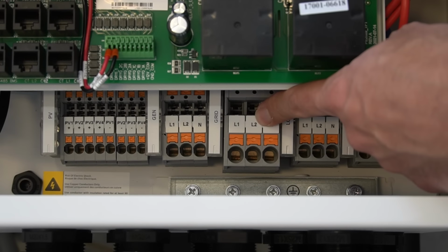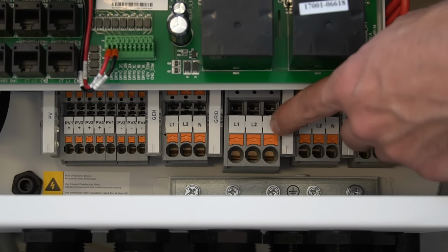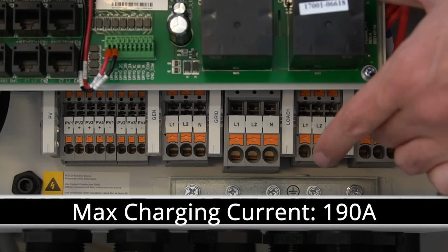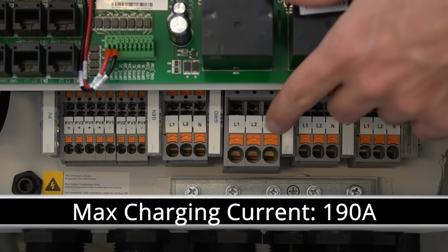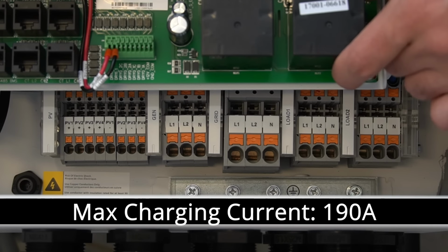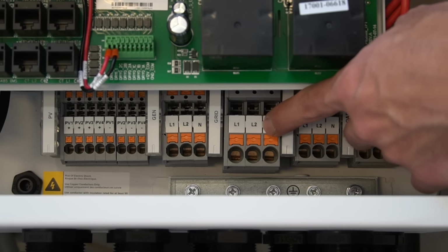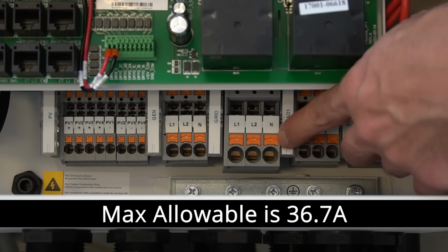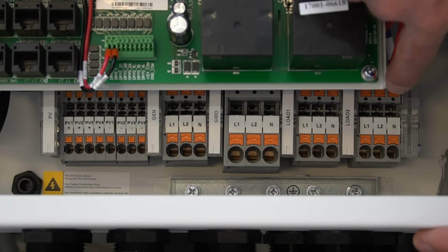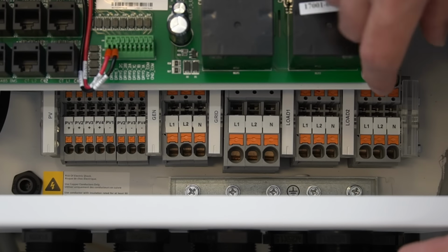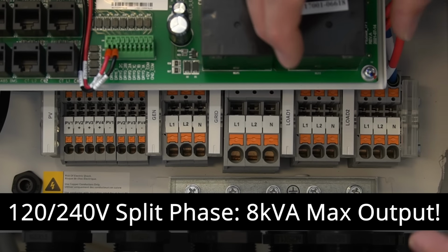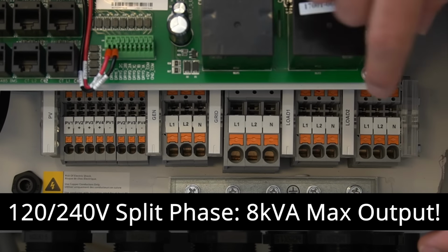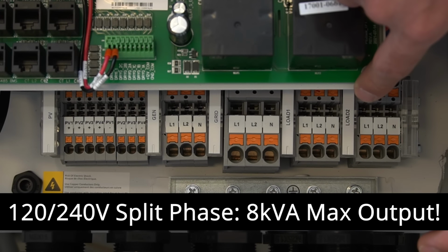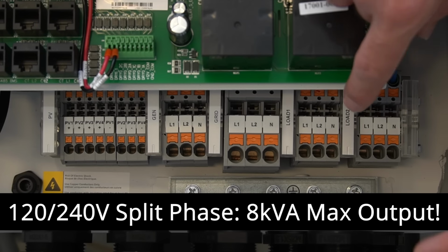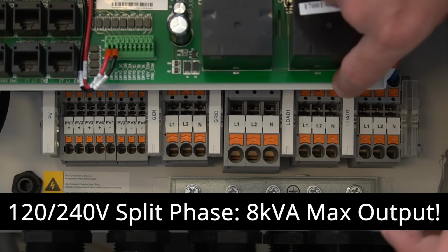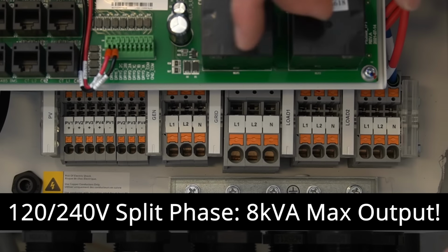Now check out how large these terminals are for the grid connection. The AC charger that's built in can actually output 190 amps at 48 volts. That's 9,120 watts. If you divide that by 240 volts, that's 38 amps. So that's why these connections are so large. Next, we have the inverter output, load 1 and load 2, and these can output together a maximum of 8 kilovolt amps. So that's 1,500 watts more than an LV6548, and it's split phase capable, so we have 120 and 240 volts. So you can run EV chargers or heat pumps or whatever you wish.